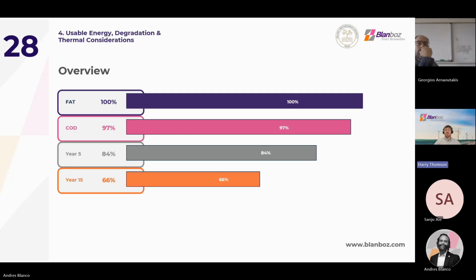We then have the BESS at its commercial operations date. This is the point at which the project is ready to deliver grid services and achieve commercial operation. Since the factory acceptance test, this equipment will have been shipped, offloaded, possibly stored, installed, commissioned, energized, and will have had to pass regulatory tests to verify compliance with the grid code. In this time, the calendric degradation, which I'll come on to discuss, will have occurred, and depending on the efficiency of the program, this can be as much as 2 to 5%.